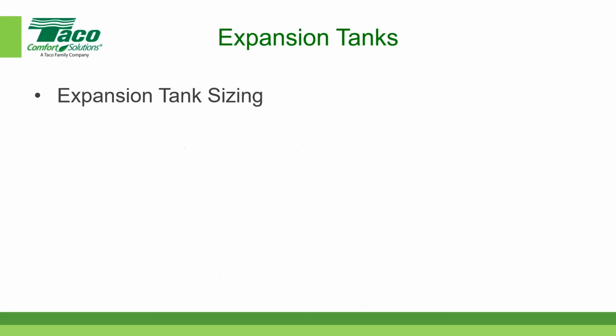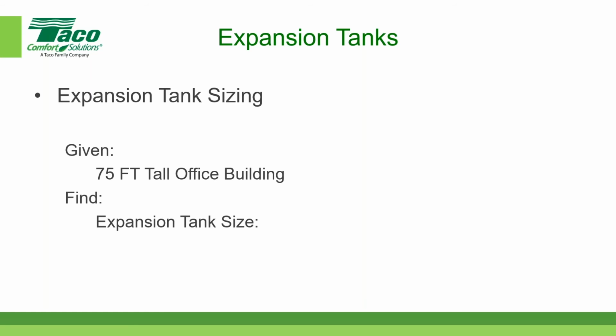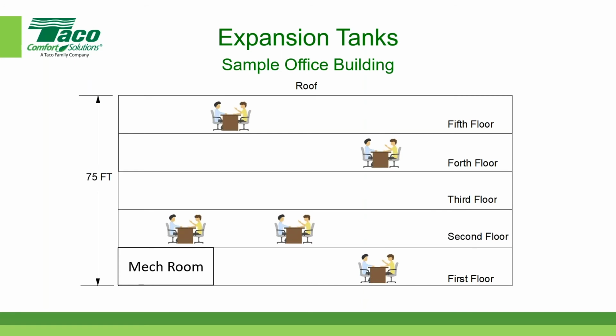So let's talk a little bit about the sizing, and let's look at the following problem. Given a 75-foot tall office building, let's find the expansion tank size. Okay, so I have a little diagram of a 75-foot tall office building. And one of the things that I just want to emphasize is that the mechanical room is at the lowest part of the building. In our case, the mechanical room is on the first floor. So we have to keep that in mind when we do some of these calculations.